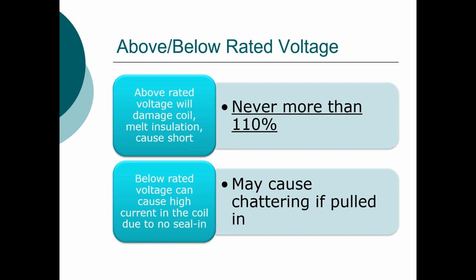Supplying below rated voltage across the coil can also have two damaging effects. First, the current in the coil is at its peak right before the armature pulls in, so the coil current at this time can be well above the rated values, and if the armature doesn't pull in, then the coil current will stay high and can burn out. Secondly, if the voltage is just at or just below the pull-in value, the relay may chatter. What this means is that it will drop in and out rapidly, which can cause pitting, carbon buildup, and high resistance at the contacts.